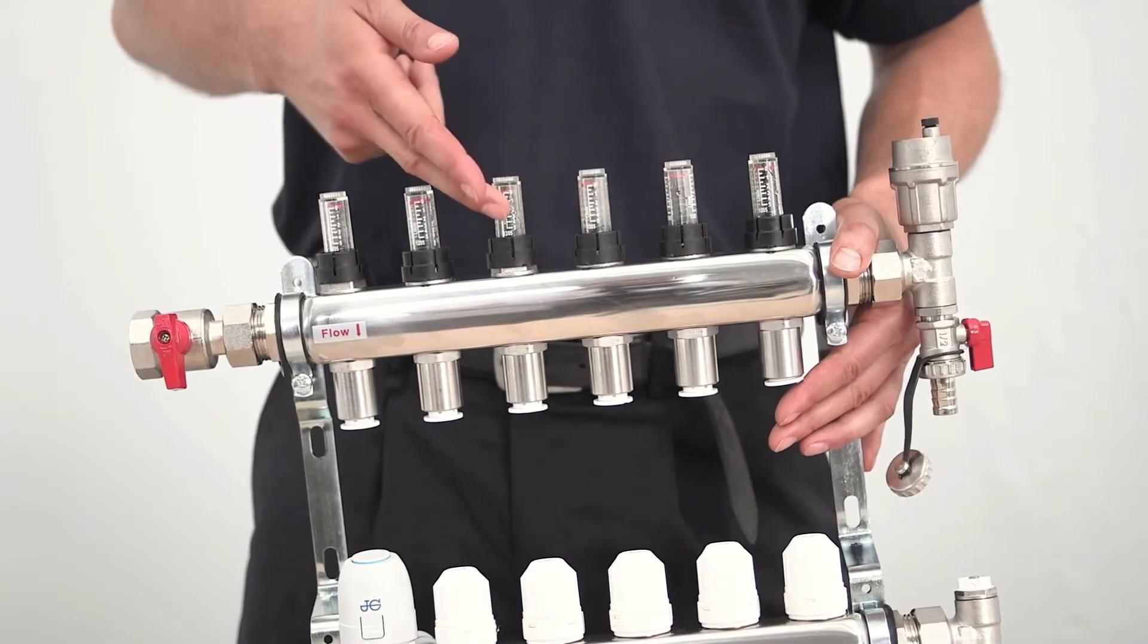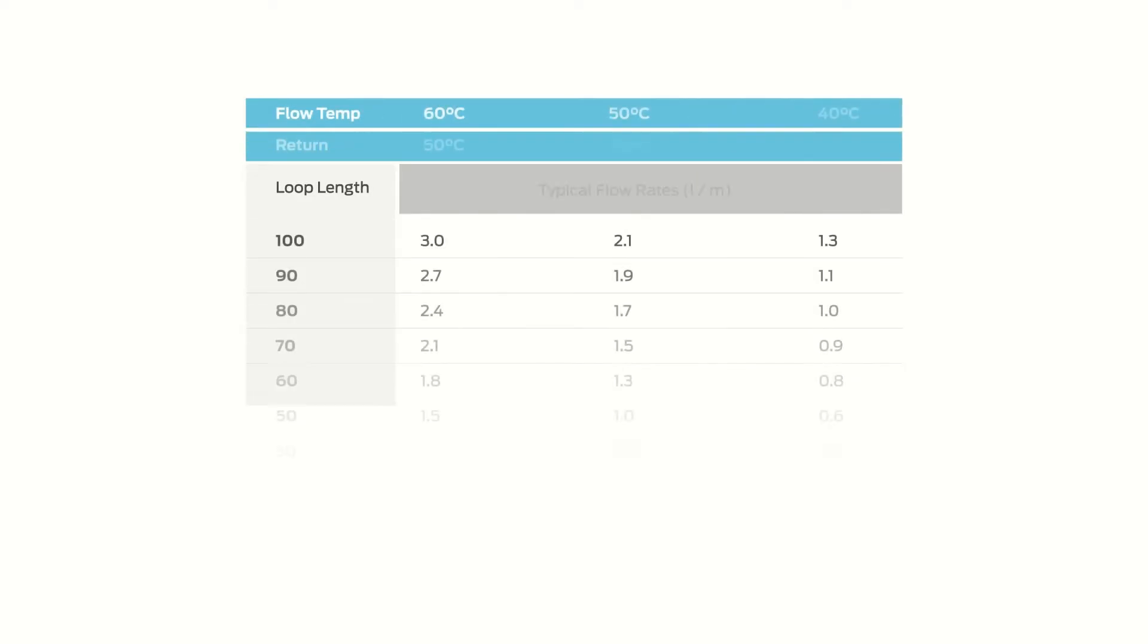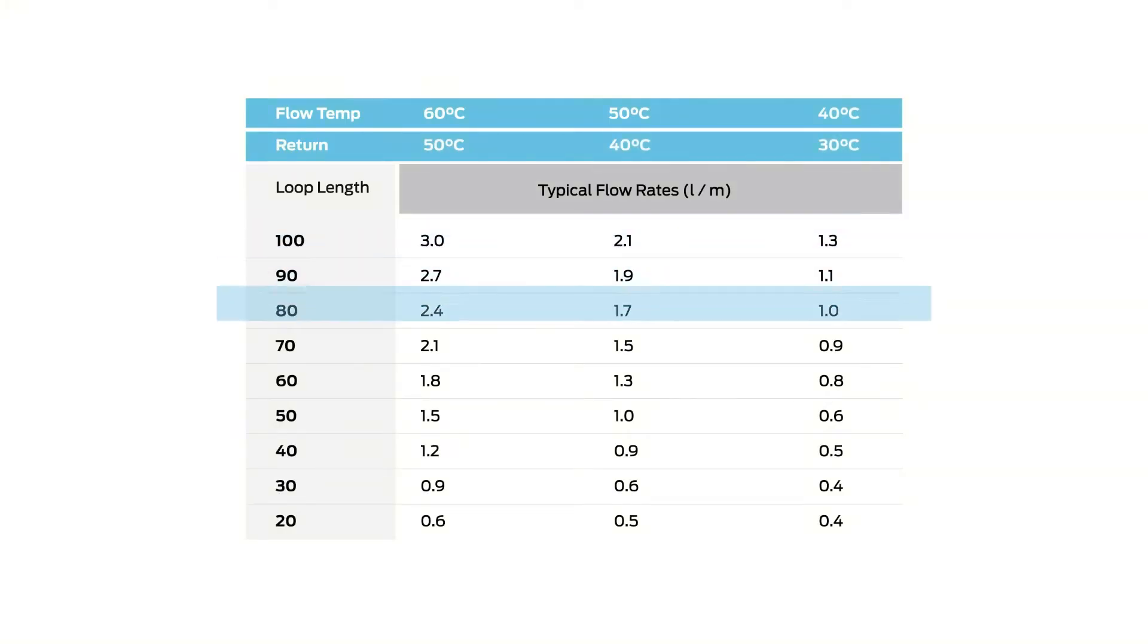The flow meters on top of the manifold give a visual indication of the amount of water flowing through each circuit. The amount of flow needed will depend on the length of the circuit and the temperature drop required. Generally, the shorter the circuit, the more restriction will be needed. This is called balancing the system.